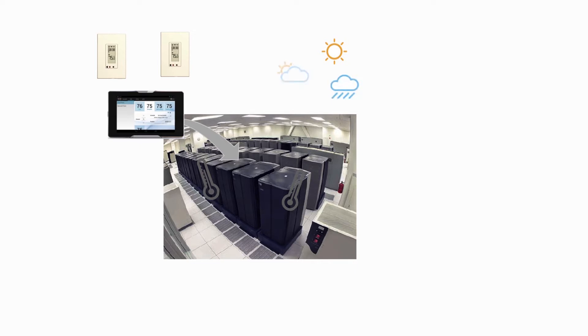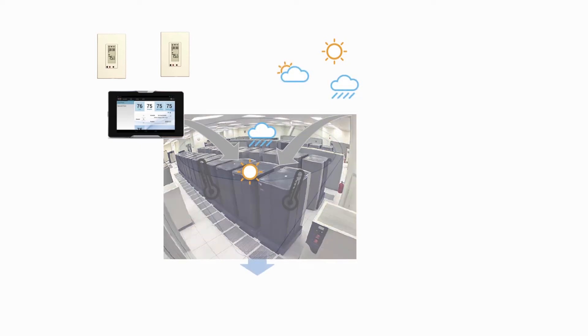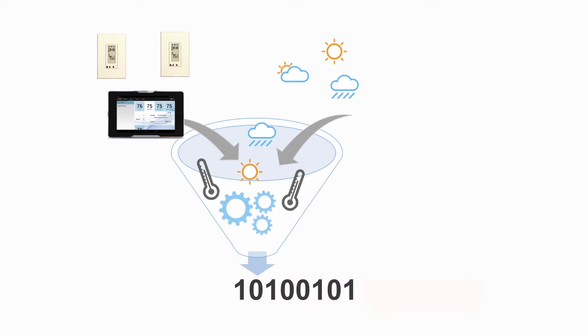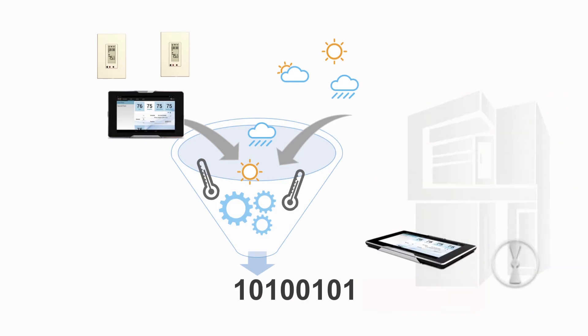Every night we could crunch this historical data and create a thermal model of the building. We could then look at the forecast weather and predict in advance how the building is going to be behaving. We could figure out an optimal control strategy and send that back into the building and that would proactively modulate the dampers to shift the conditioning air to parts of the building that need it before the temperature errors actually occur.